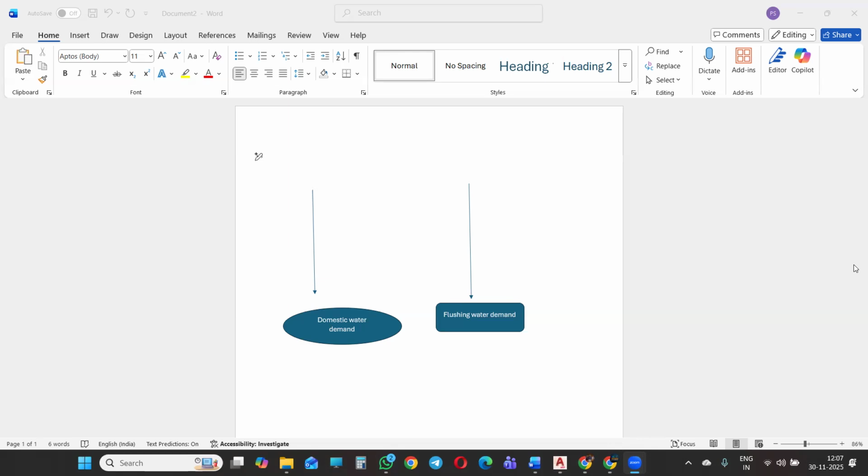But practically, 100% water demand is also not used, because if 60-80% population is there and you designed for 1,000, then the water is also going to waste. So we have to make the bifurcations part-wise, part 1, part 2, or part 3. In the first phase, this much population will be there, then the bifurcation will be X. Second part, Y. Third part, Z. When 100% occupancy is there, you open that valve, and the full capacity can be used.